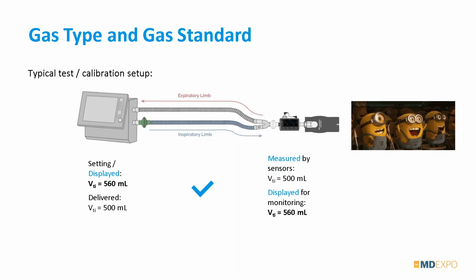If your ventilator's not delivering in BTPS, and it's not always obvious, you might have to look in that manual. You might have to actually contact the manufacturer, but make sure you do so that you can make sure you're measuring in the same gas standard that the ventilator is delivering in or displaying in. Okay? Questions about this? Has anybody faced this problem before? No one?